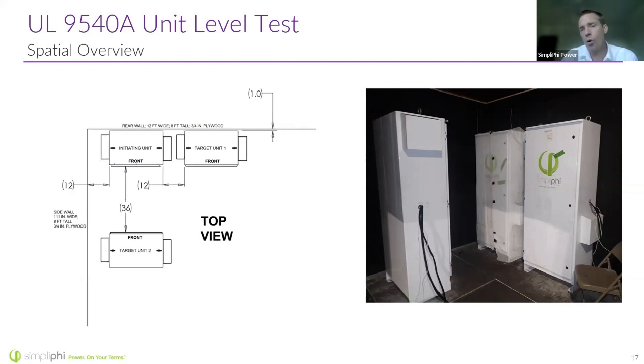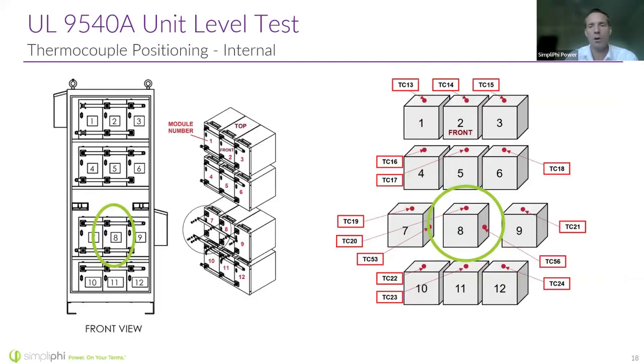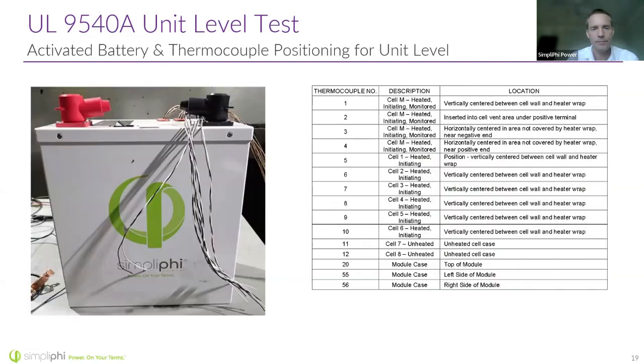And the presence of these walls is to actually replicate a room, because having those walls there, they keep the heat in and keep these units at higher temperatures, right? Which was similar to the installation they might be in at a site. Okay, so yes, it was battery number 8. We're looking at battery number 8, and we're going to heat this up. We're going to measure the temperature on the casings of all the batteries around it as well. And so we've got many different thermocouples there, 24 different thermocouples, looking at just surface temperatures of the other batteries as we go through the test.